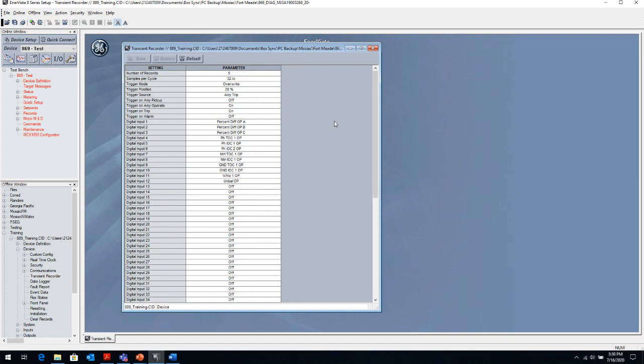Because a relay could trip, but it could trip, we call that a trip but unexpected. So it could be a correct trip, but undesirable, in that it actually didn't trip because of the way I set it up. It tripped for a different reason. So even for a correct operation, you might want to take a look at what's going on with the relay, because in a future incident, it might be the opposite, where it might not trip for what you want it to.